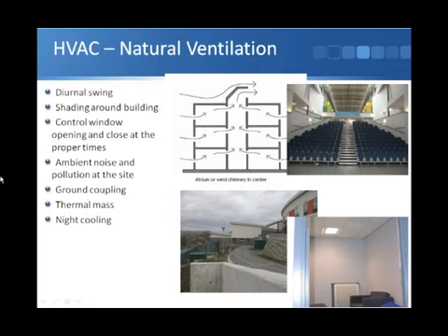It might bring the air in through some other mechanism, but if we are using windows, we don't want them open all the time, because we may end up losing more heat than we gain through an opening window situation. And there are issues such as ambient noise and pollution to think about, and that will affect where we might have the openings. And in some cases, it may be necessary to avoid natural ventilation altogether, of course.